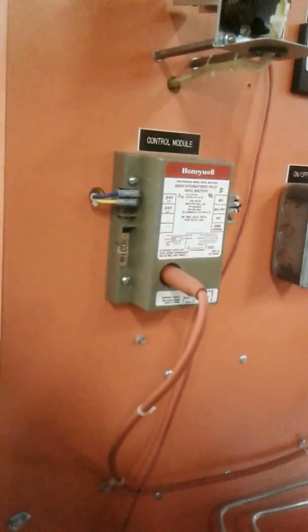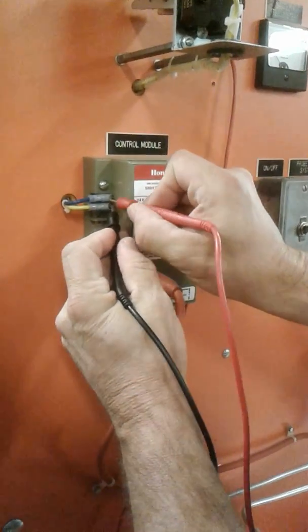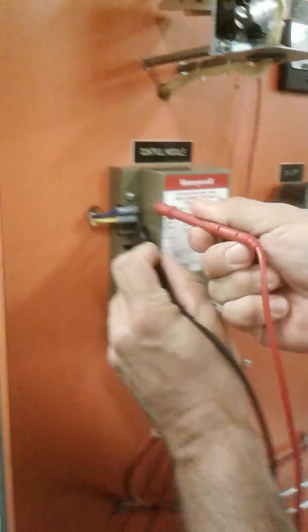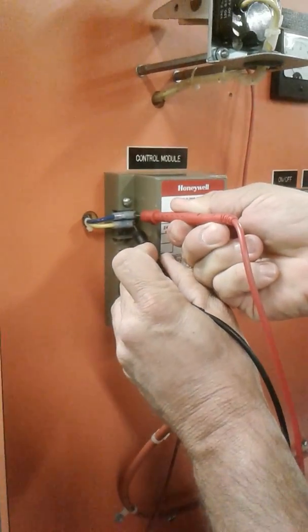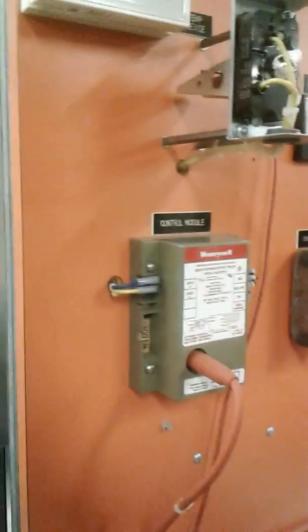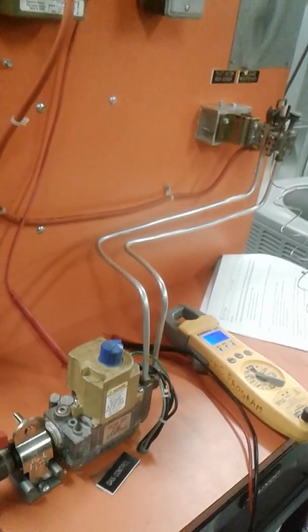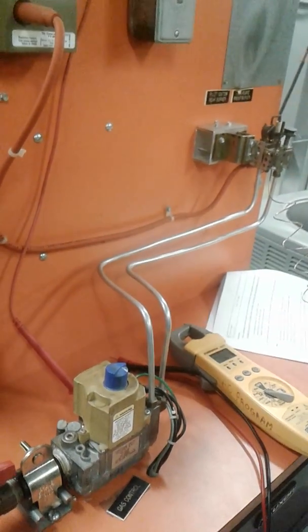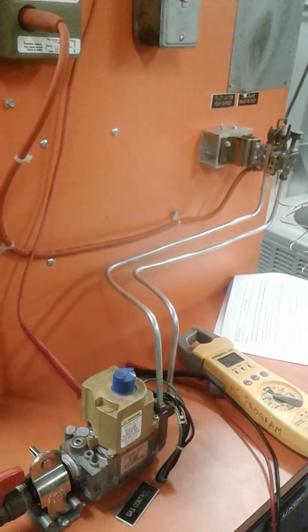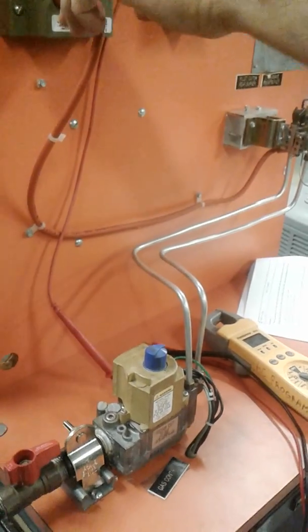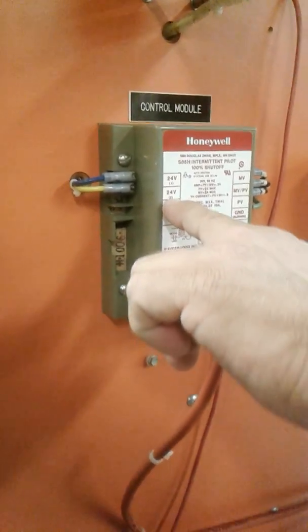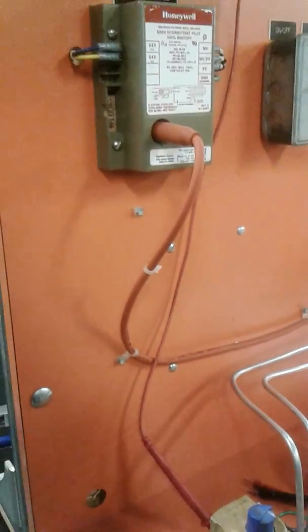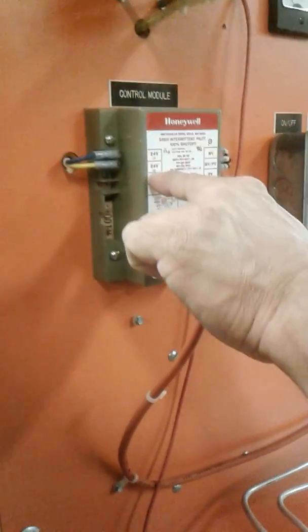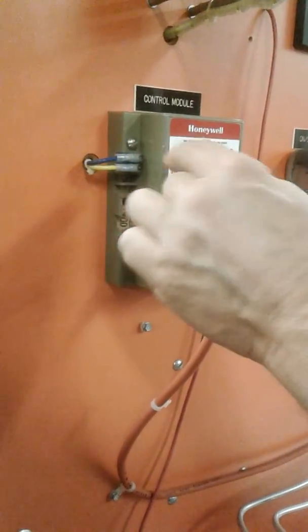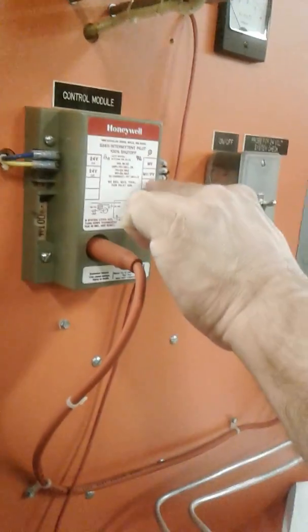Let's see if we got our voltage coming into our control module. So we're working our way backwards as we're troubleshooting, okay? What do I got again? Yep. So what's wrong, guys? So 1 is the supply. That's the power supply. The switch 1. So it's gonna come from the back. What did you say? Transformer. Did you hear that, guys? Look what it says. He's right. It's 24 volts. We're not getting 24 volts to our control module. We need to have 24 volts supplied to our control module to open up our pilot valve.